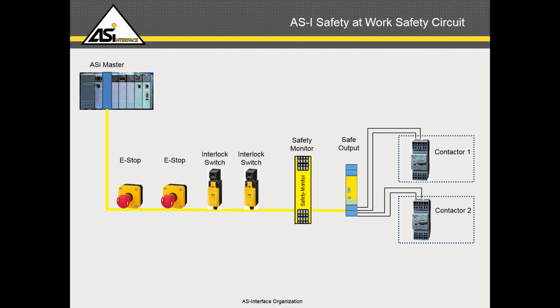Now the AS-i Safe system allows itself to attach the switches directly to I/O safety modules, or directly to the safety cable itself. The nice thing is, anything that can host an AS-i master becomes a safe system. So you don't necessarily have to go into a safety PLC situation and the safety software that would be required, because that's an increase in cost of hardware and in terms of software licenses.